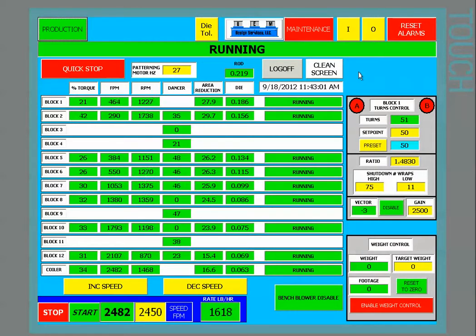Down below to the right we have a weight control software package that isn't being utilized at this time. Bench blower enable disable button. We have buttons to increment and decrement the speed, and then we have the main control at the lower level here: stop, start, speed setting, and it gives a rate in pounds per hour.